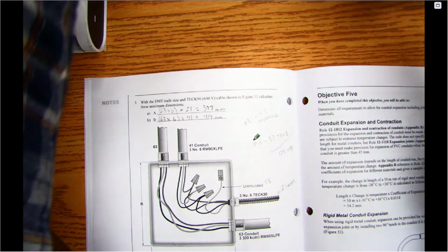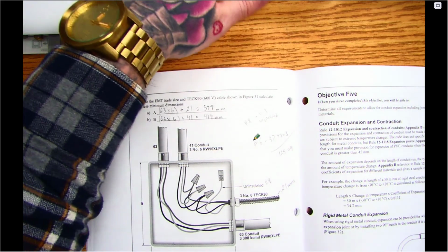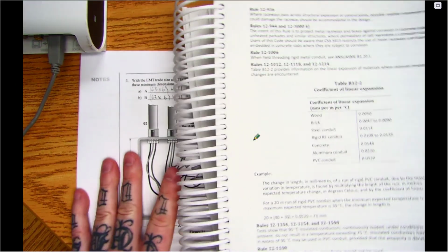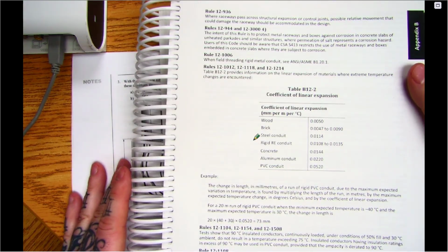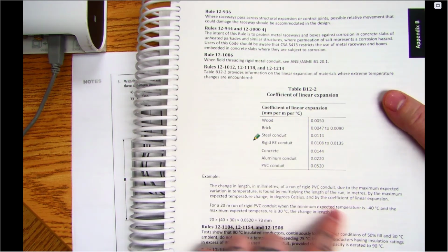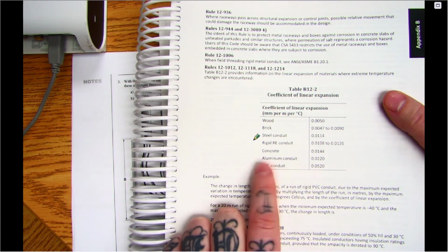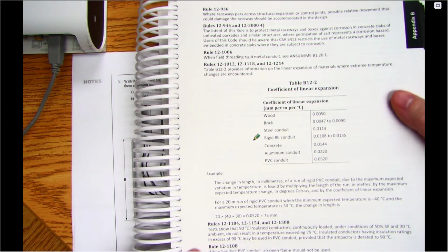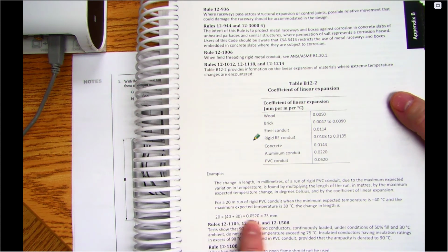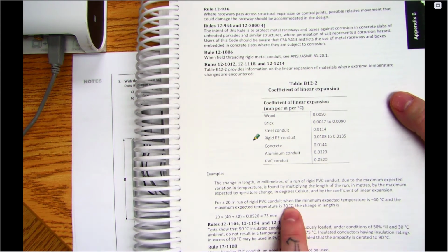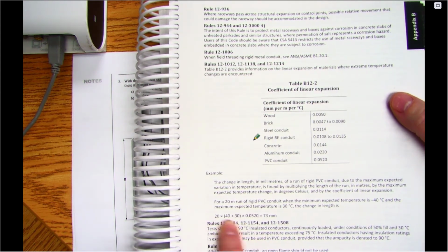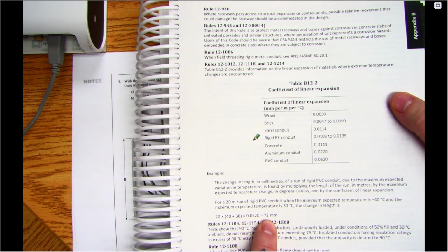I think it's appendix B. So right here, it's got all the different coefficients of linear expansion, whether it's wood, brick, steel conduit, rigid, RE conduit, concrete, aluminum conduit, PVC conduit.